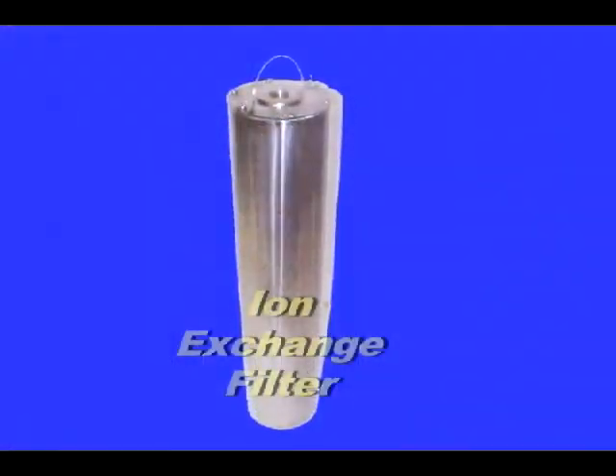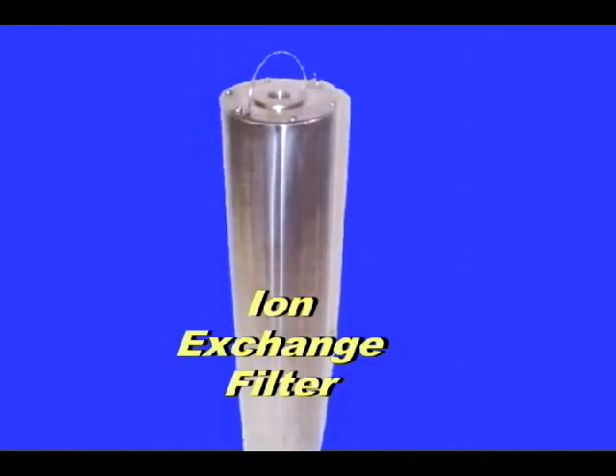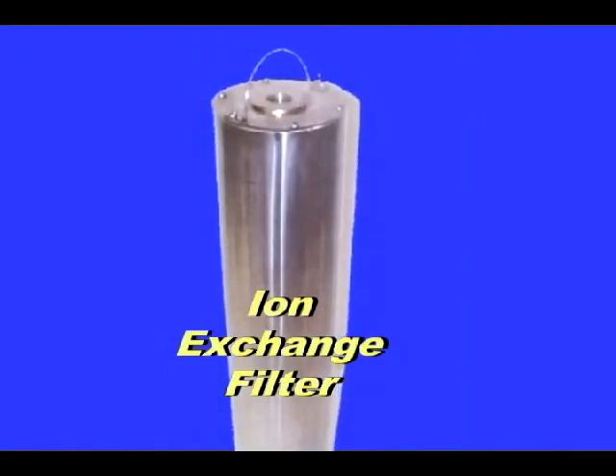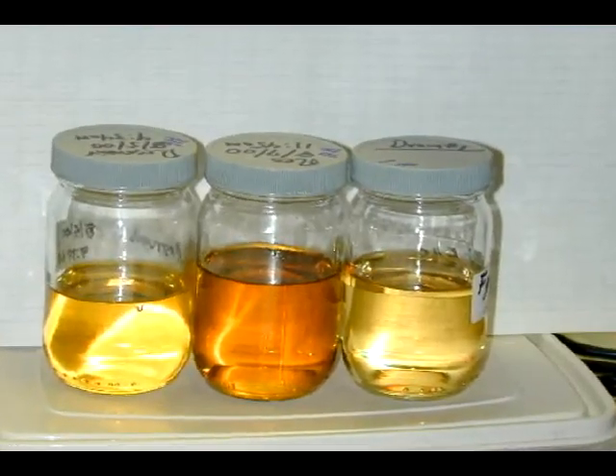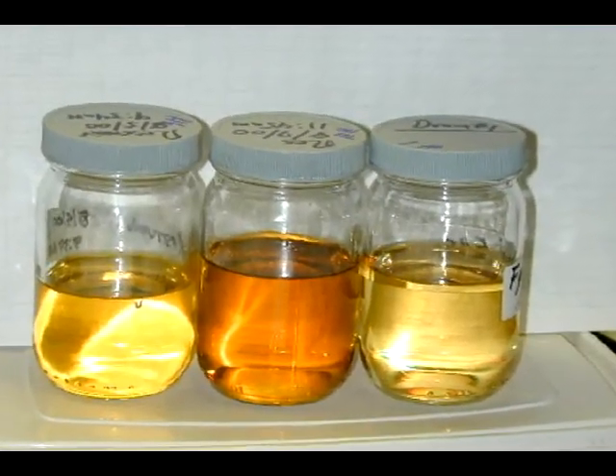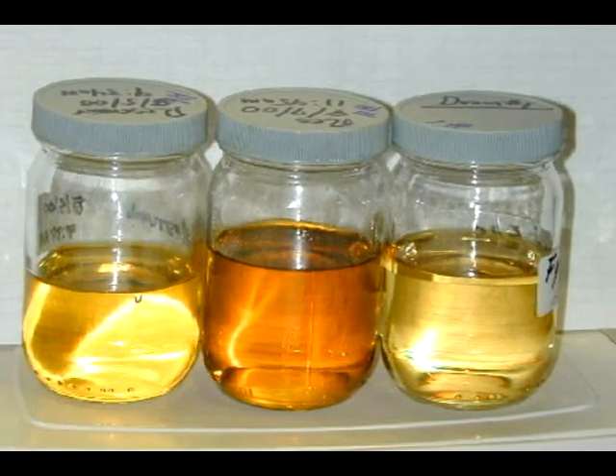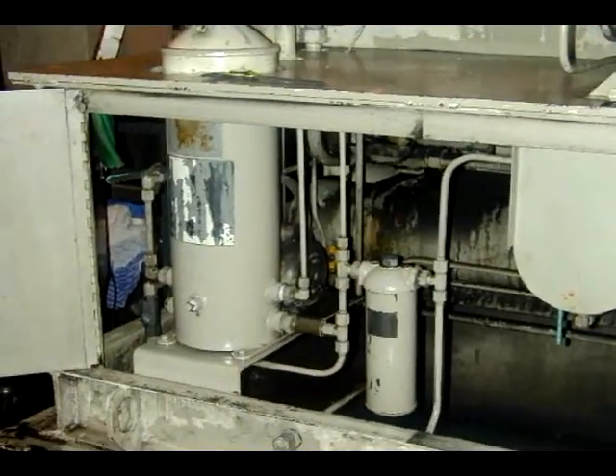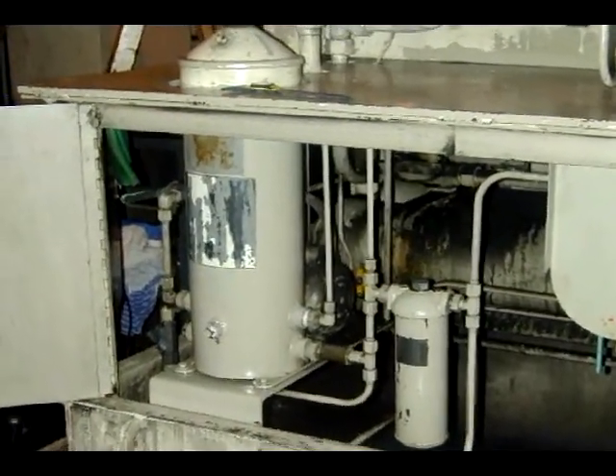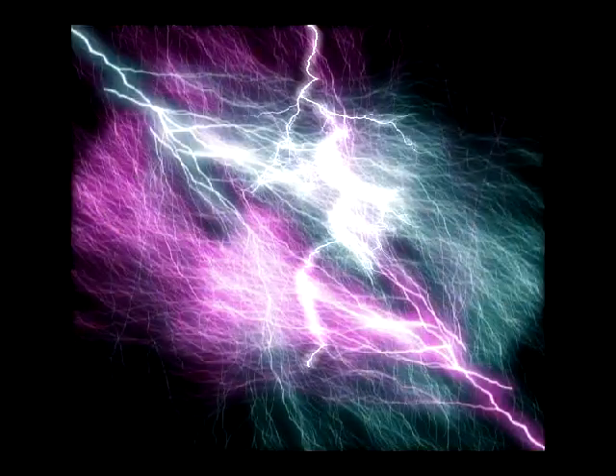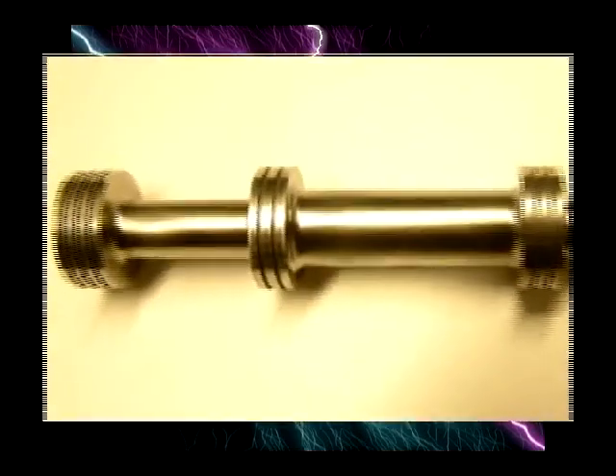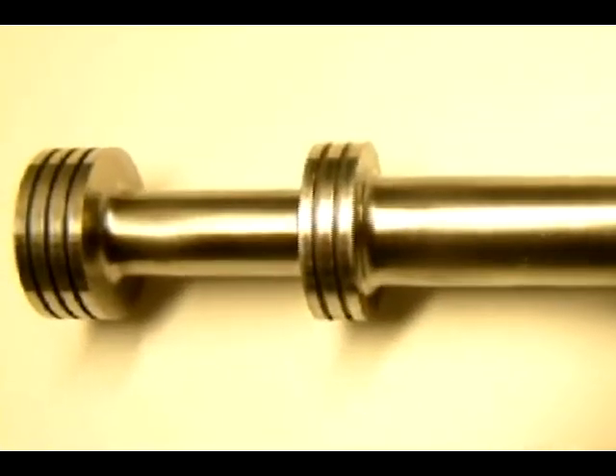Recently, ion exchange filters have been used in place of Fuller's earth and Selexsorb filters to control the acids in FRF. Ion exchange filters do not release any metal salts, therefore do not cause any gel or varnish formation. However, ion exchange filters can compromise or reduce the resistivity, or resistance to conduct electricity, of an FRF fluid. Low resistivity can cause etching of the servo valves.